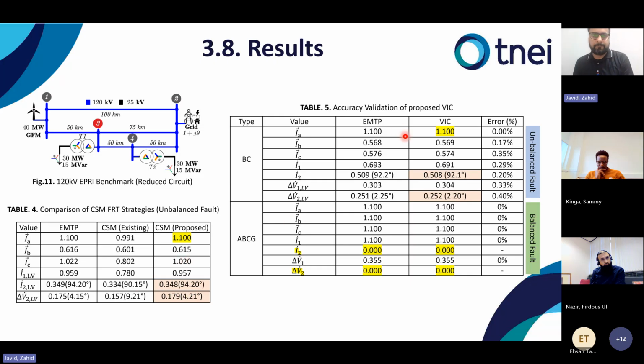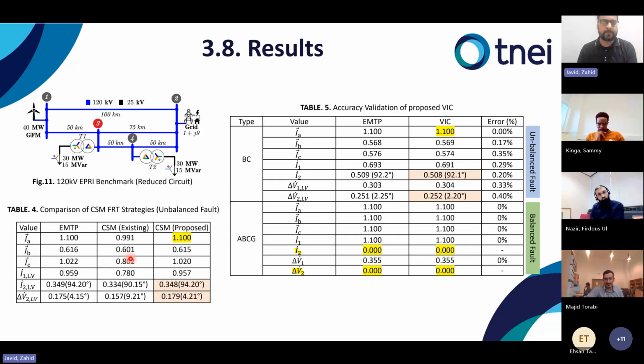And also if we see the validation of the virtual impedance control, this is for an unbalanced fault. We can see that for the unbalanced fault, the angle difference is 90 degrees between the negative sequence current and negative sequence voltage, and the positive sequence current is greater than the negative sequence current, which is also the case for the current saturation method. And for the balanced fault, we can see that there is zero current injection, because for a balanced fault there is no negative sequence, so there will be no negative sequence current injection. So we can see that this also works for balanced faults.